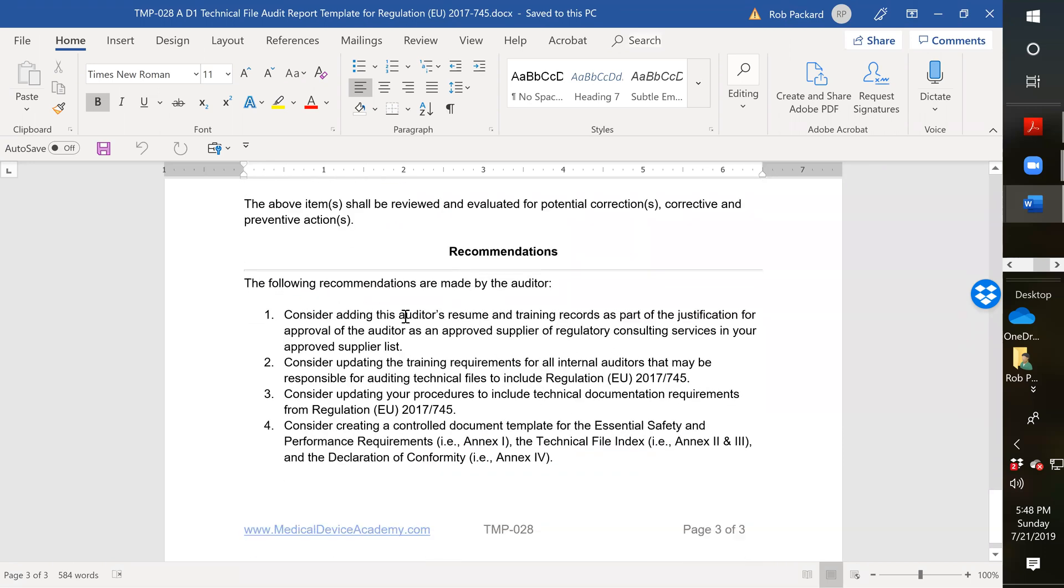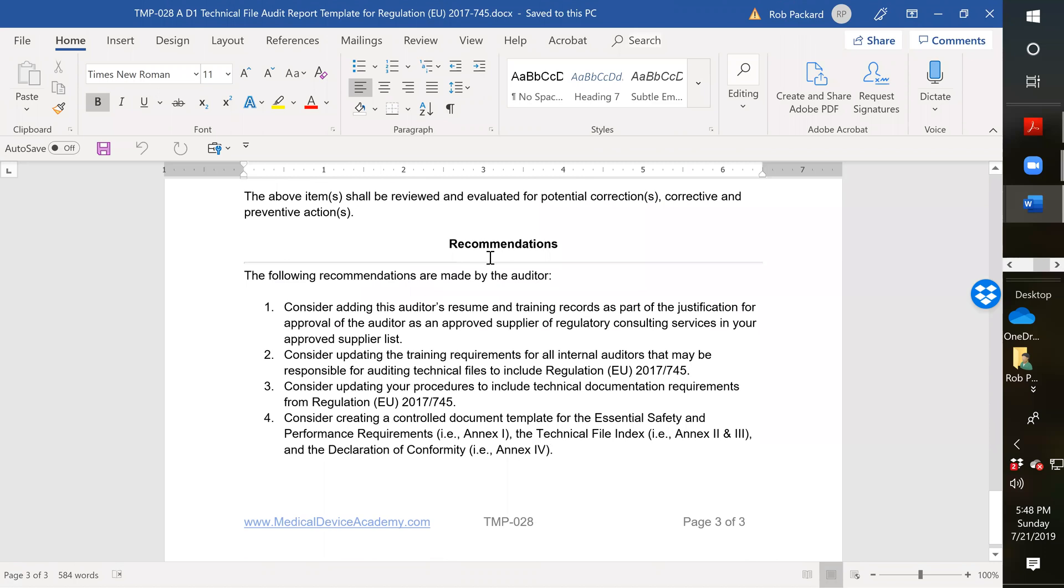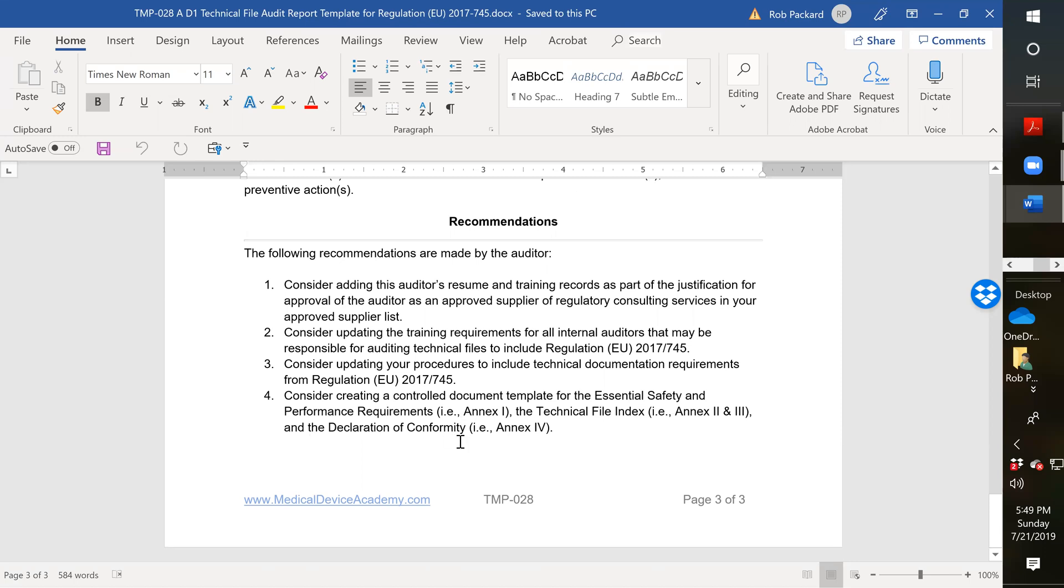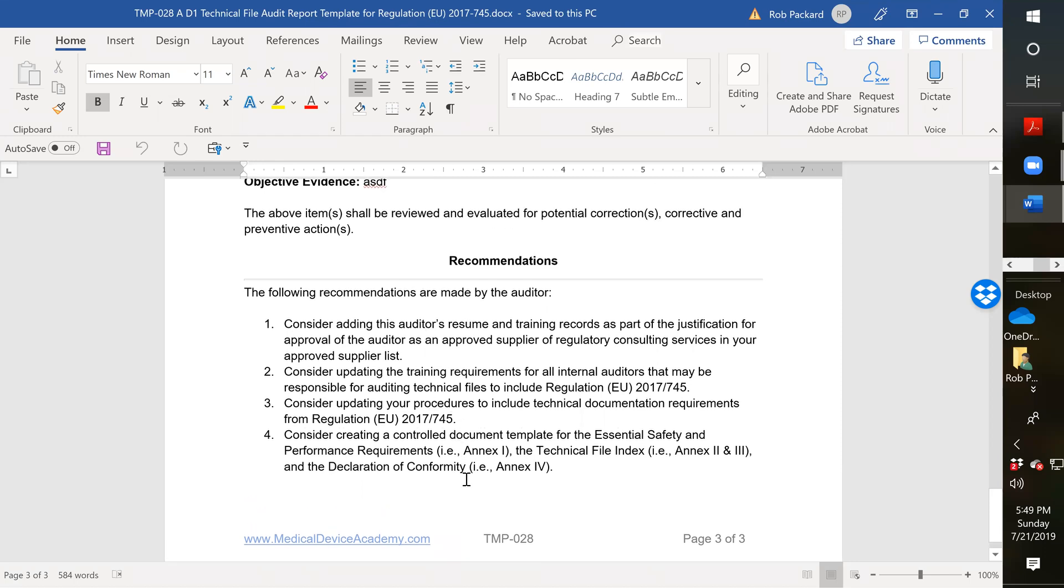And then at the bottom here I have some standard boilerplate recommendations. Whoever's doing the audit, you might want to include, remember to include their resume and training records as part of your approved supplier list and the documentation or objective evidence of how you selected them and approved them as a supplier. Because you're required to have records of supplier approval even for consultants. Number two, you want to update your training requirements for all your internal auditors to make sure they've been trained to Regulation EU 2017 745. You want to make sure all your procedures are updated to include the technical documentation requirements. And then last but not least, you want to make controlled, brand new controlled templates for the essential safety and performance requirements, the technical file index if you use an index, and the declaration of conformity. So those are the key things that I'm recommending as sort of boilerplate requirements.